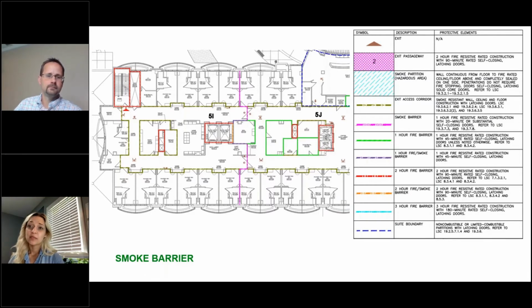This is a healthcare occupancy, so we're looking at the 5th floor, and you can see 5I and 5J. That's 2 separate smoke compartments on this wing of this hospital. So we have a smoke barrier that carries a 1-hour fire resistive construction, which kind of catches people up, I think, a little bit. But it's going to be separating these 2 smoke compartments. So if there's a fire on one side, they can move hospital patients to the other side of the smoke barrier to shelter in place, to give more time for potential evacuation of the building, or whatever the egress strategy is for that floor of the hospital.